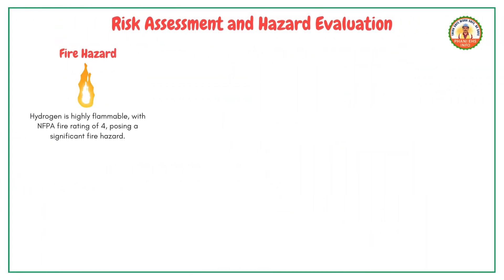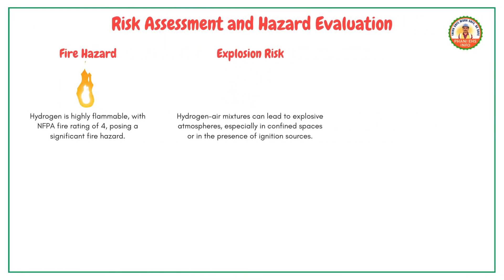Risk assessment and hazard evaluation. Let's assess the risks associated with hydrogenation reactions. Fire hazard: hydrogen is highly flammable with an NFPA fire rating of 4, posing a significant fire hazard. Explosion risk: hydrogen-air mixtures can lead to explosive atmospheres, especially in confined spaces or in the presence of ignition sources.